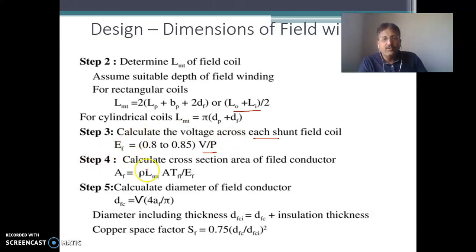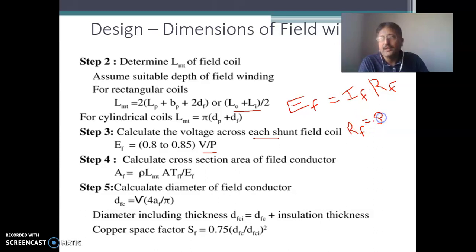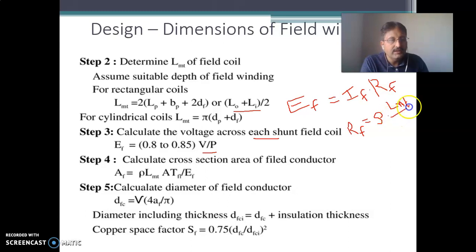Once you get EF (voltage per coil), the next task is to find out the cross section area AF. The equation is: EF = IF × RF, where RF = ρ × LMT / AF (resistivity × length of mean turn / area). Substituting: EF = IF × ρ × LMT / AF. Making AF the subject: AF = ρ × LMT × IF / EF. This gives the equation for the area of the shunt field winding conductor.